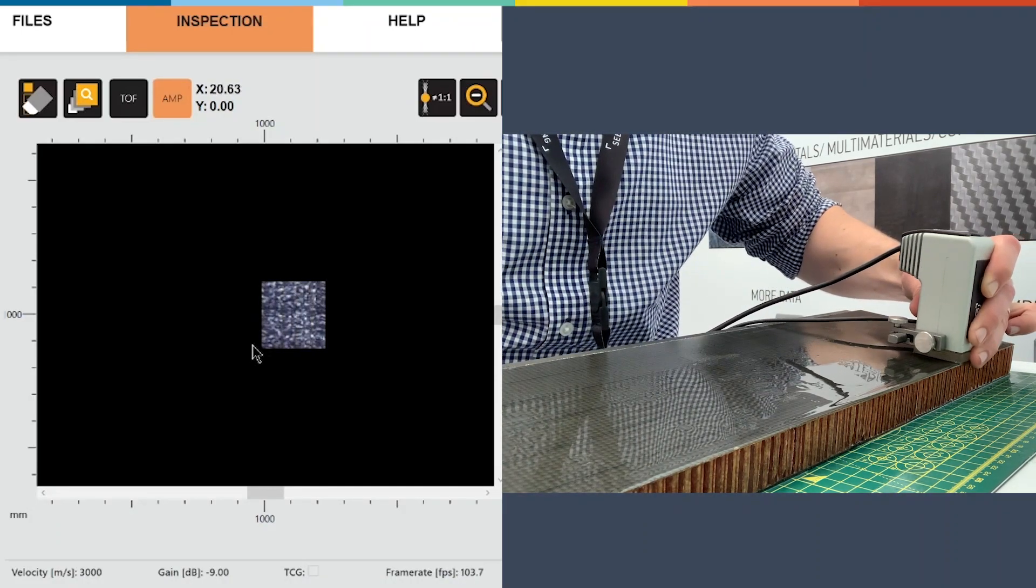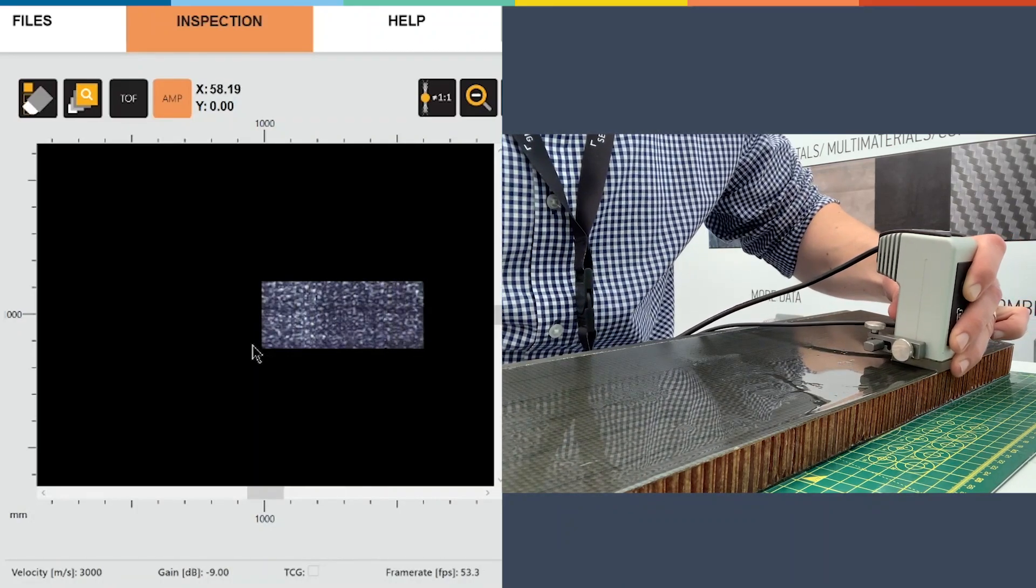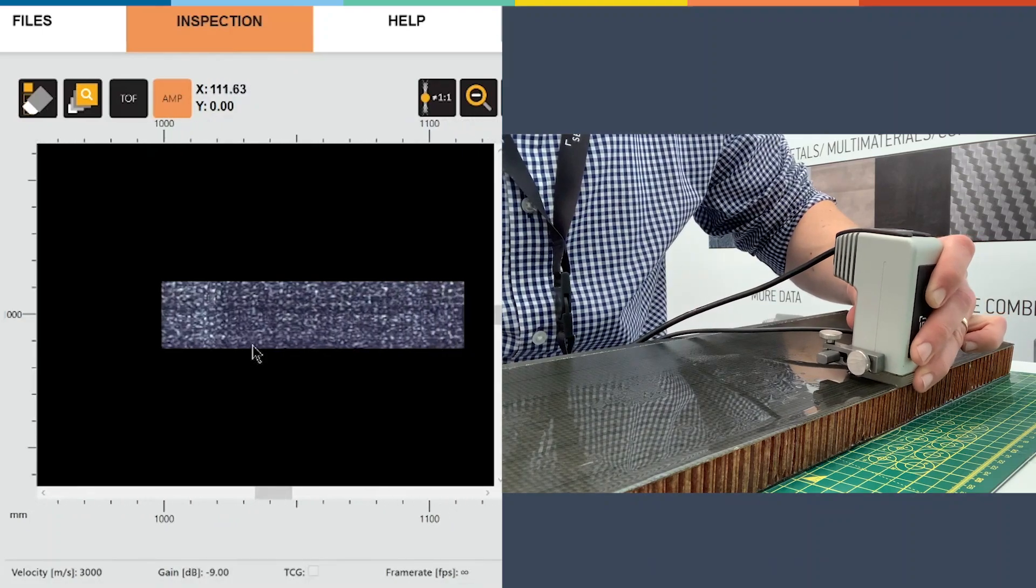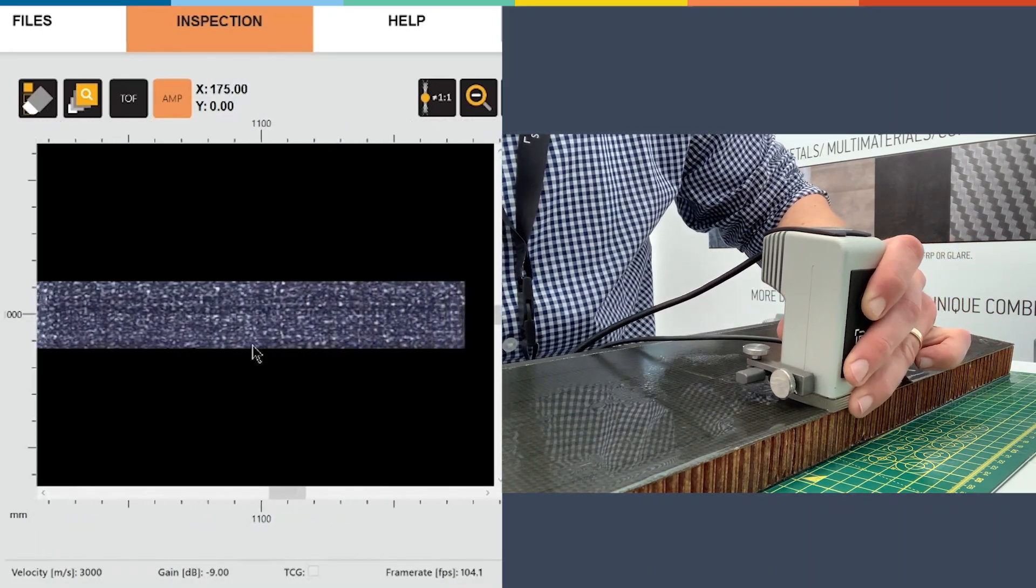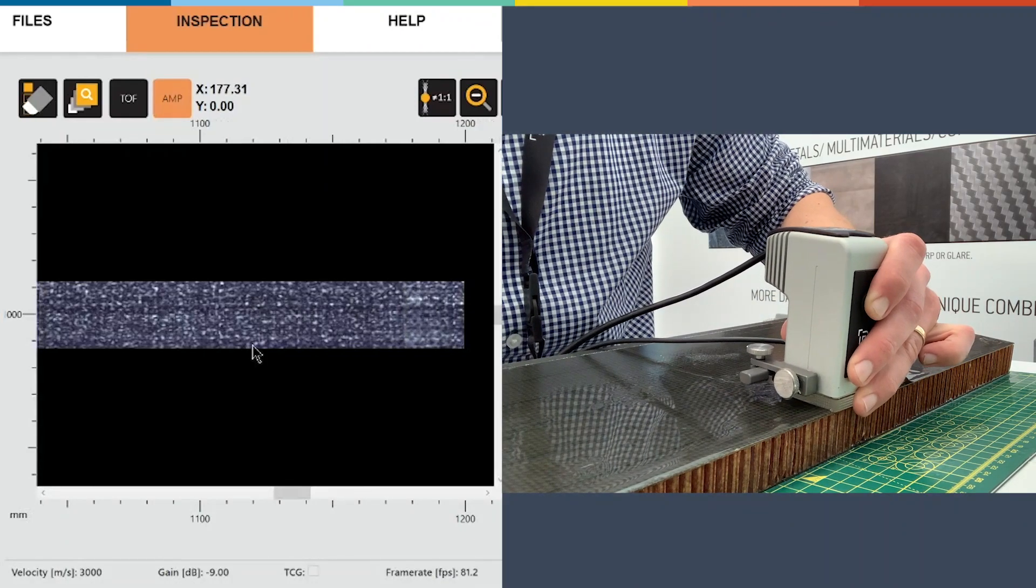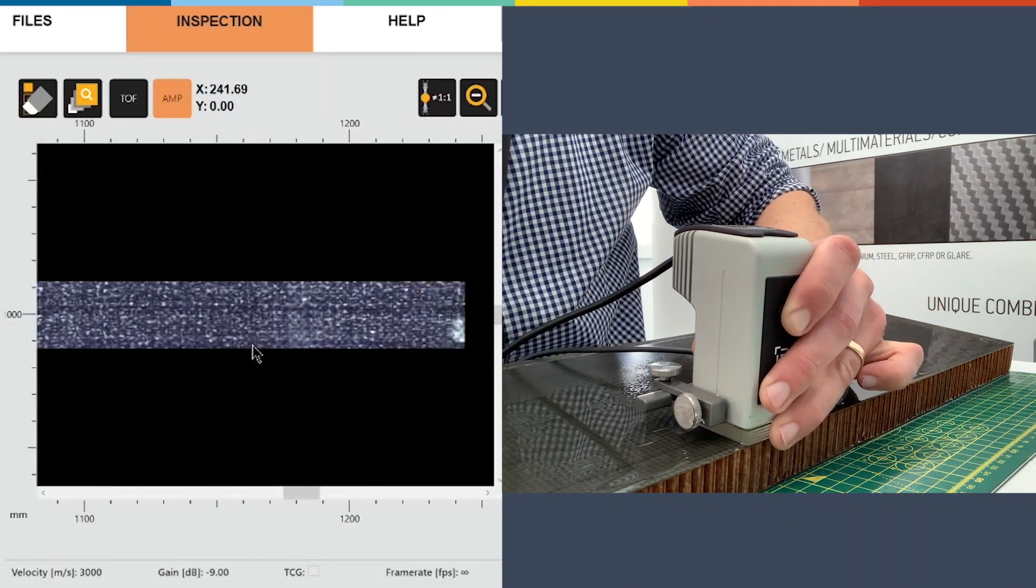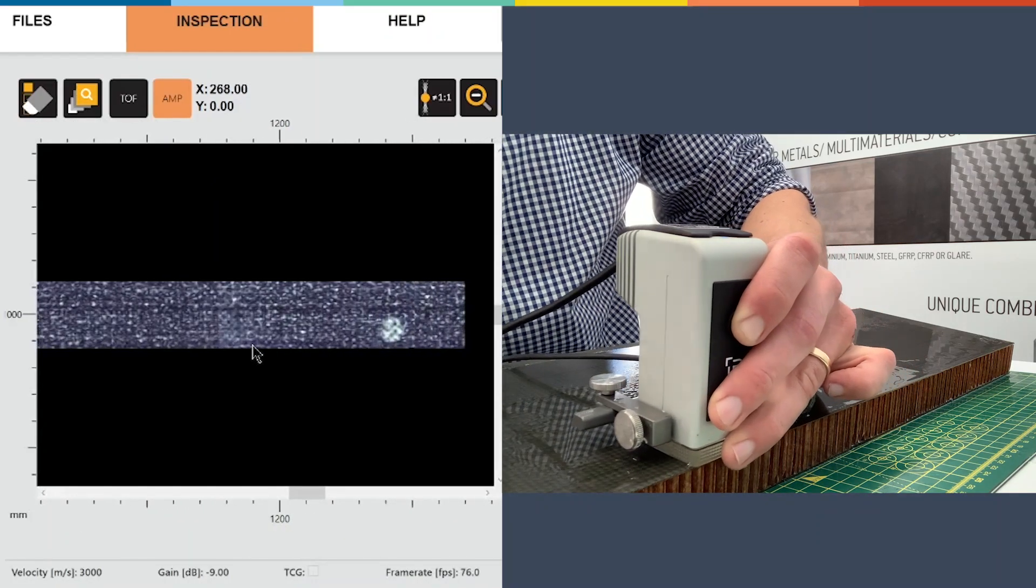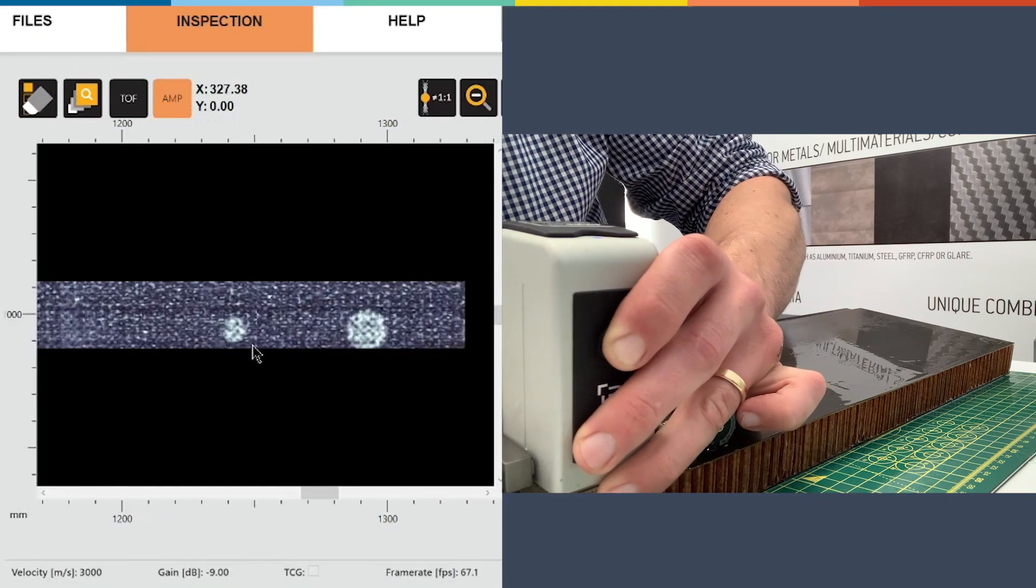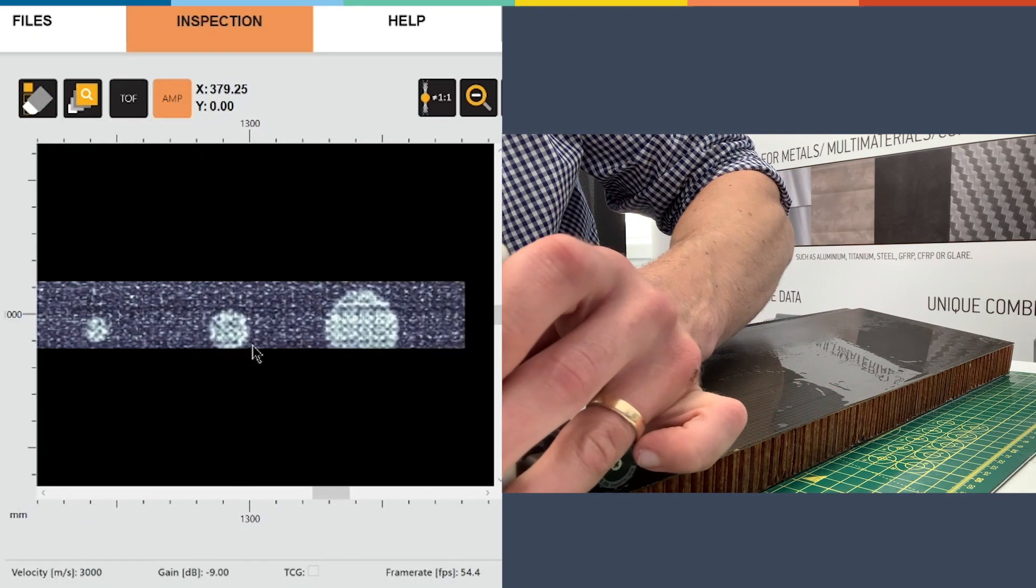I'll start moving over. There's no need with the software to preset your C-scan area because you can see that it just updates as I move. If we have missing data it appears as black lines, so you can easily just go back and collect the extra data lines as needed.